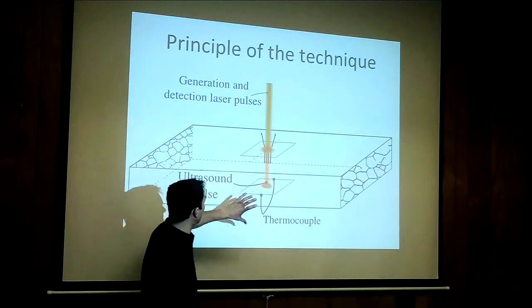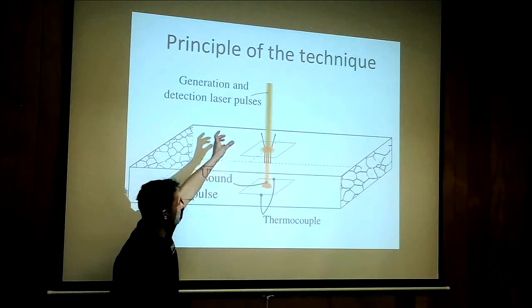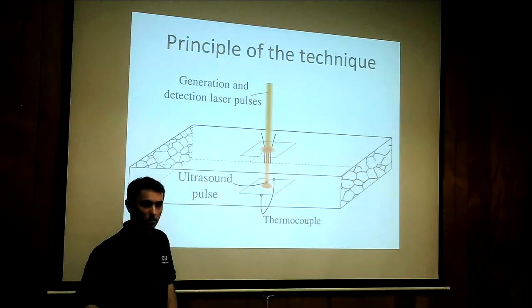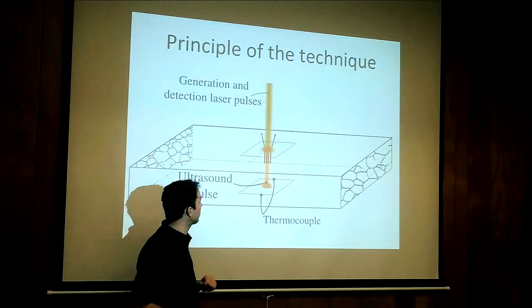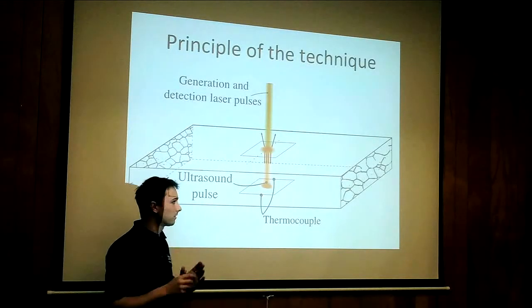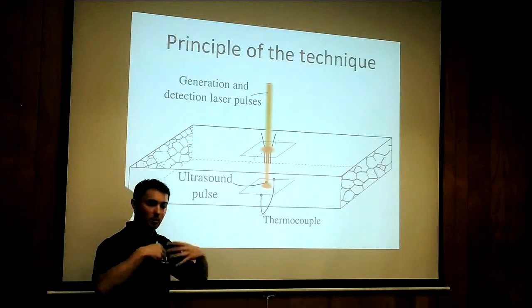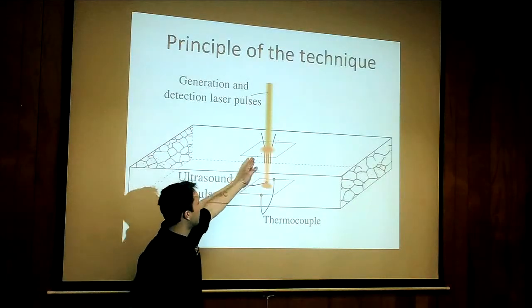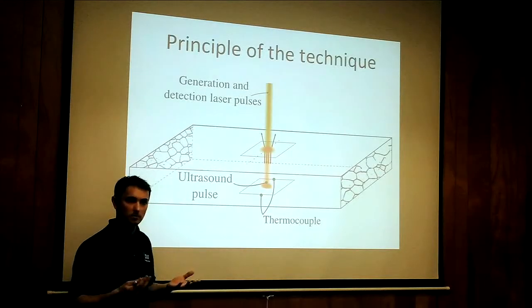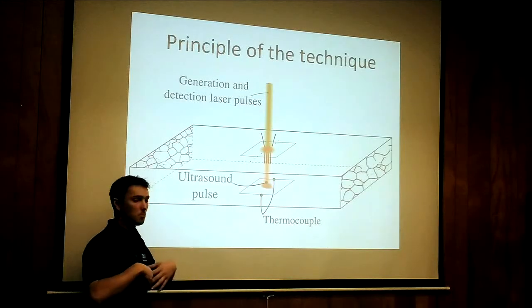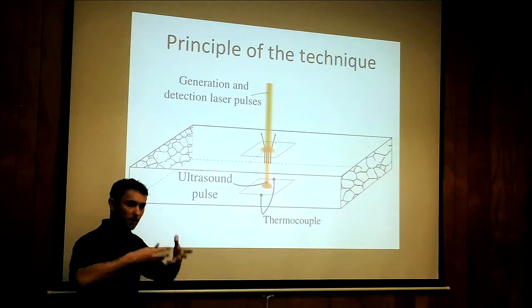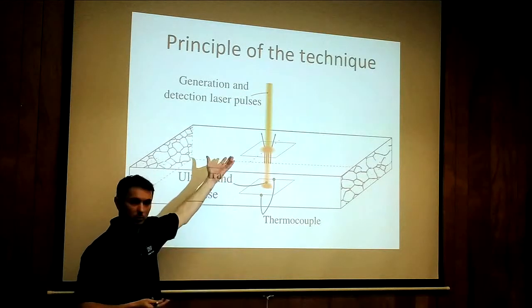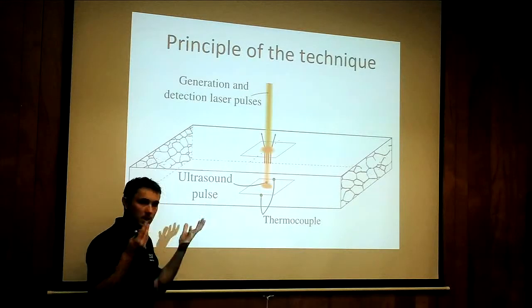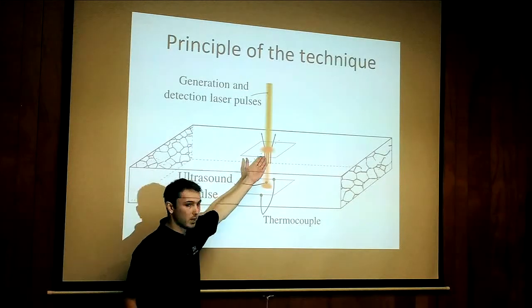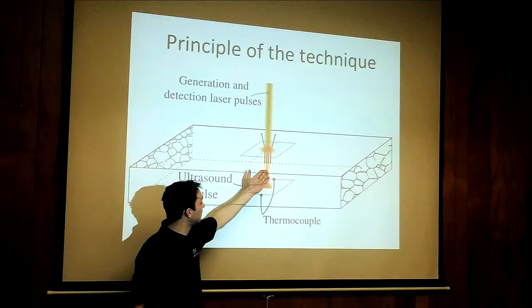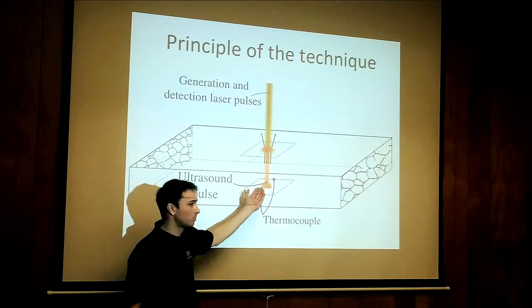What we see here is a plate with lasers that fire onto the sample. There are two lasers. The first laser has a very short duration and is going to vaporize a little layer of the sample. This evaporation of metal ions forms a plasma, and this plasma expands very rapidly out of the surface of the sample. This very rapid evaporation creates a pressure wave inside the material that propagates perpendicular to the surface of the sample.